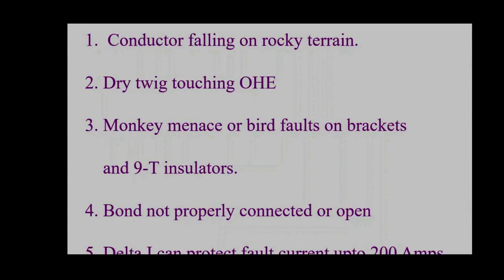Some examples they have mentioned. Conductor falling on a rocky terrain. So rock, it's not a perfect conductor. It's not going to have a very low resistance and a very high fault current. Therefore, that's an example where only delta I can detect.